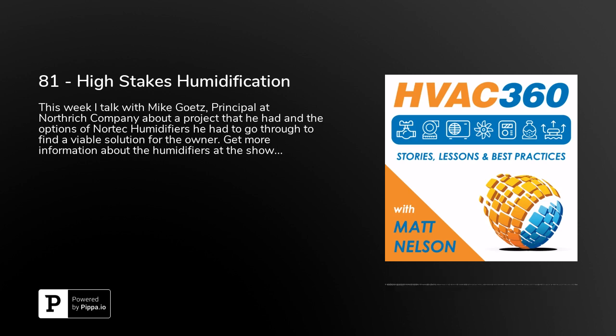Well, actually that's the issue. It's not necessarily undersized, but there's approximately six humidifiers coming up with that load. And because they have maintenance issues, there's typically one or two of them down a lot. So with that, of course they're going to be short. And then also the events and the things that have happened in the facility have changed. So you have more economizer mode, so you have more load requirement than they probably originally intended. It's not terribly undersized, but I think now would be the time to add it, because it's inexpensive to add now. We just add some additional heads.